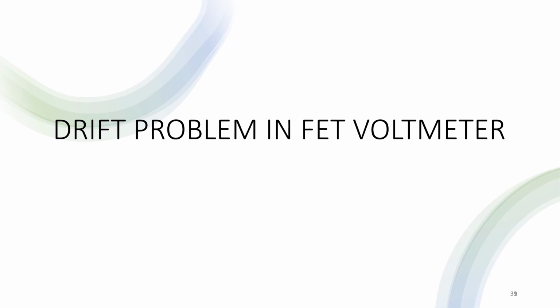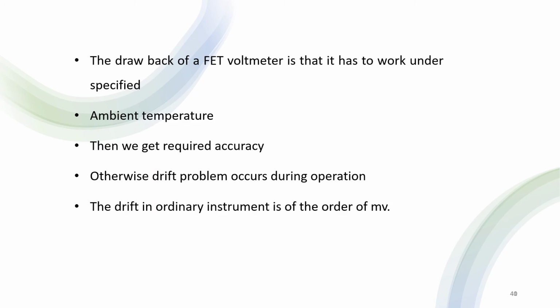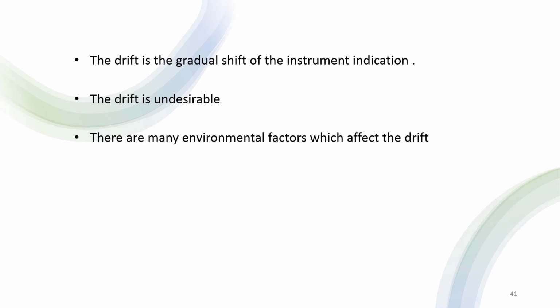The drift is the gradual shift of the instrument indication over an extended period during which the value of the input variable does not change. So the drift is undesirable because the readings are not precise and they may change. There are many environmental factors which affect the drift. These factors are the stray electric field, the stray magnetic field, the temperature changes, the contamination of the metal, etc.